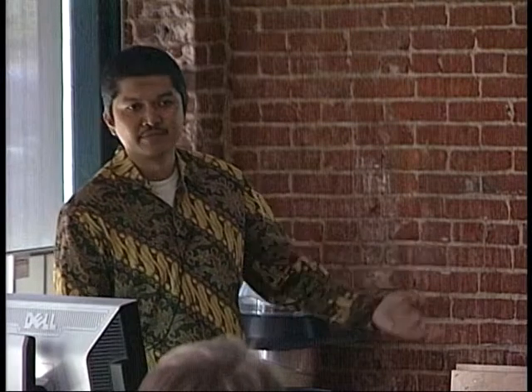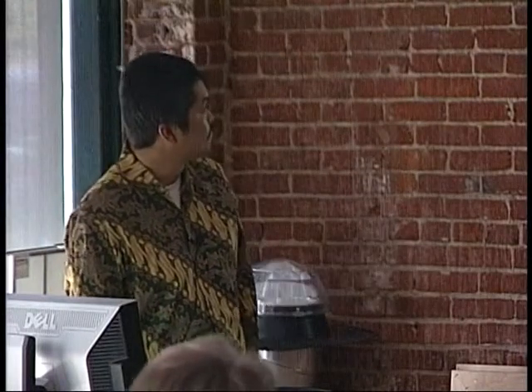The design calculation says it's 3.2 tons. As you can see, the peak is right about there. The blue and the brown here are the effect of external shading. If you take out the shading, this is what you get. And it's not significant because this is on the north side. So it's insignificant anyway. If it were on the south, it should be significant.